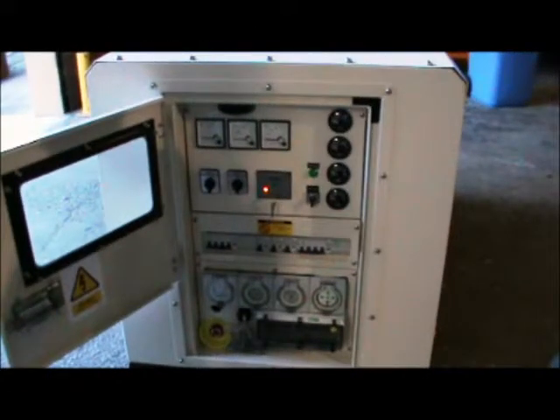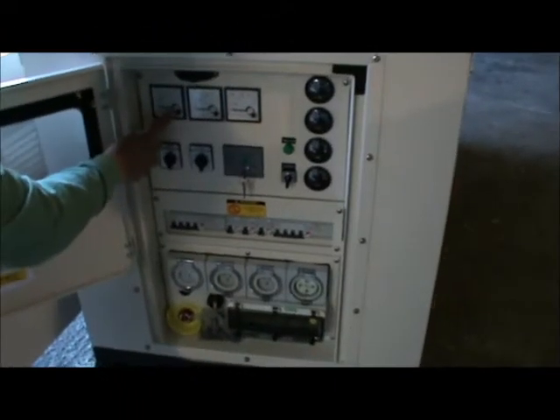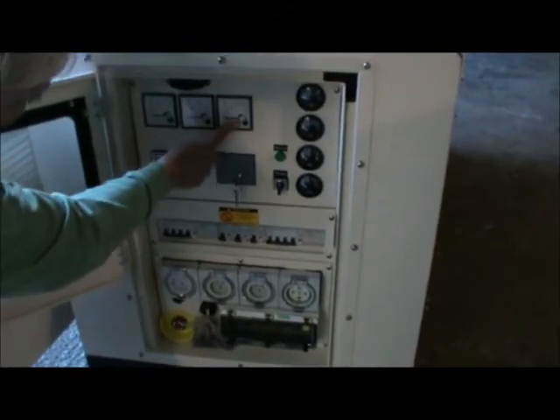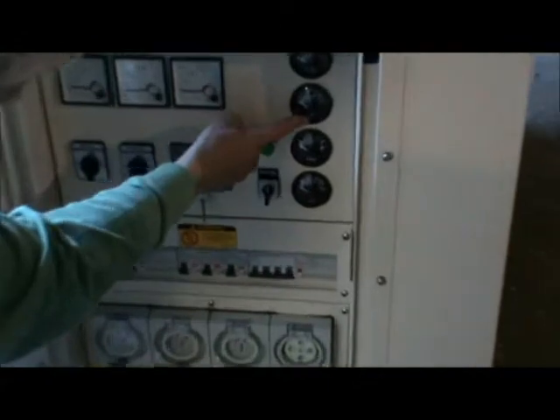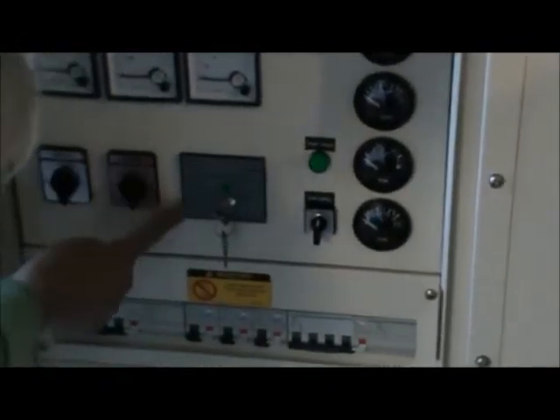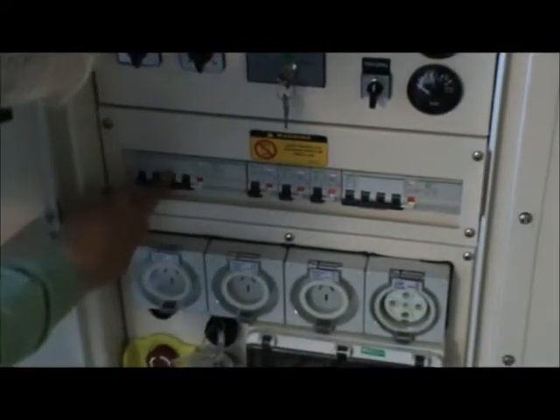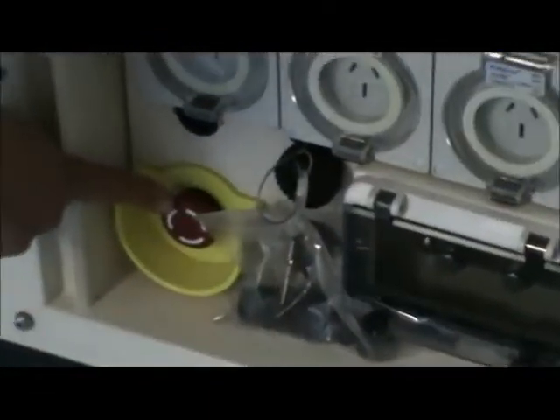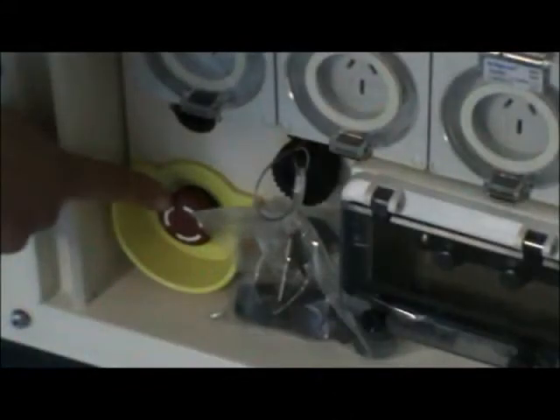The AU specs model uses a Deep Sea 702 control panel system with key start. The control panel readings will give you information on the amps, volts and hertz being produced by the generator. Oil levels, temperature, fuel levels and battery isolator output. The key start with warning lights. Voltmeter and ammeter preset output levels. Circuit breaker. Both 1-phase and 3-phase power sockets. And most importantly, an emergency stop button.